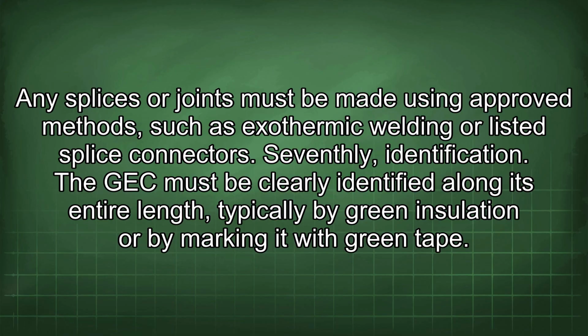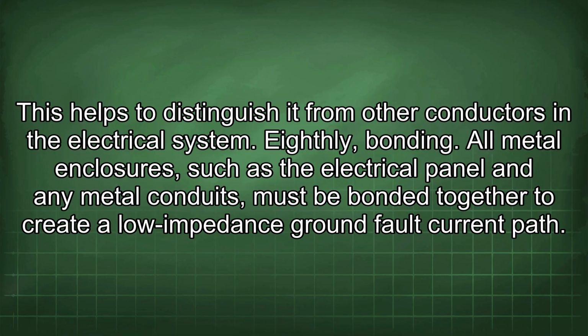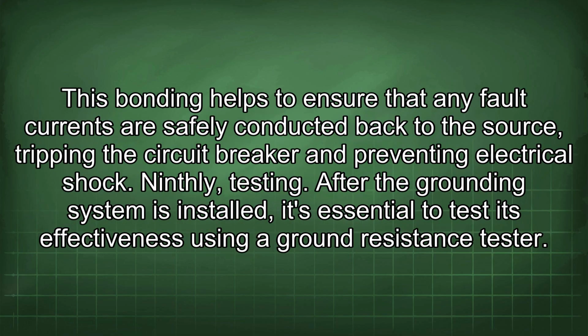Seventhly, identification. The GEC must be clearly identified along its entire length, typically by green insulation or by marking it with green tape. This helps to distinguish it from other conductors in the electrical system. Eighthly, bonding. All metal enclosures, such as the electrical panel and any metal conduits, must be bonded together to create a low-impedance ground fault current path. This bonding helps to ensure that any fault currents are safely conducted back to the source, tripping the circuit breaker and preventing electrical shock.